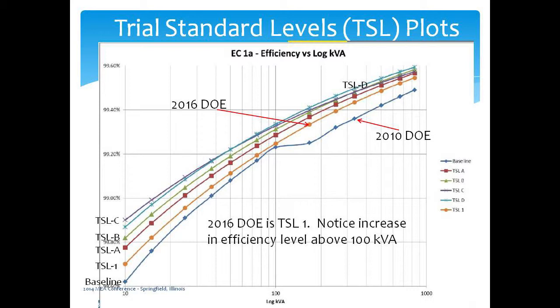They did it at a baseline, then went up for each standard level, calling them A, B, C, and D—higher levels of standard. What we have now is this lower baseline. But you can see when 2016 rolls around, they move to the TSL level 1, and that gap above 100 kVA is where you'll see a major shift in the size and weight of units. It took a big jump in that particular area of efficiency levels.